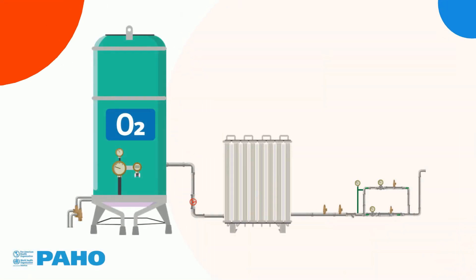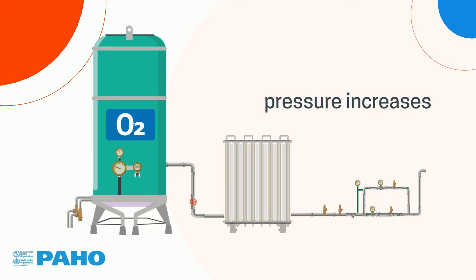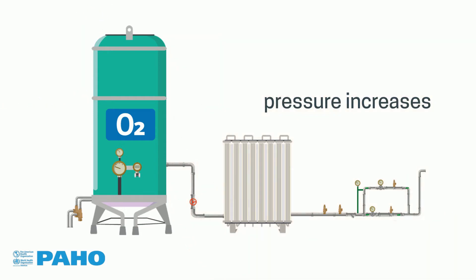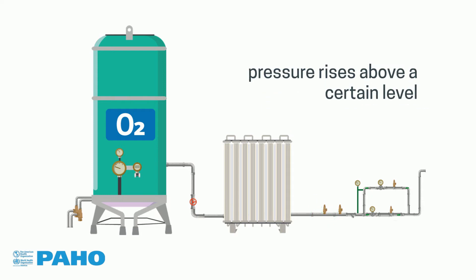When liquid oxygen is being gasified, its pressure increases. To prevent accidents, the gasifier is on a circuit with a safety valve that is activated whenever the pressure rises above a certain level.